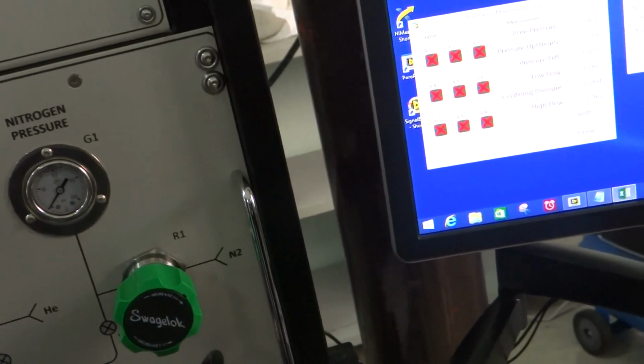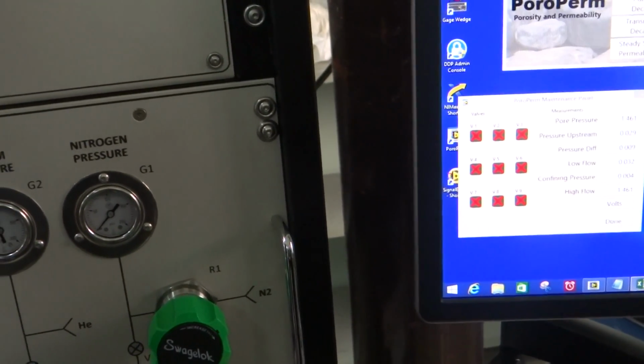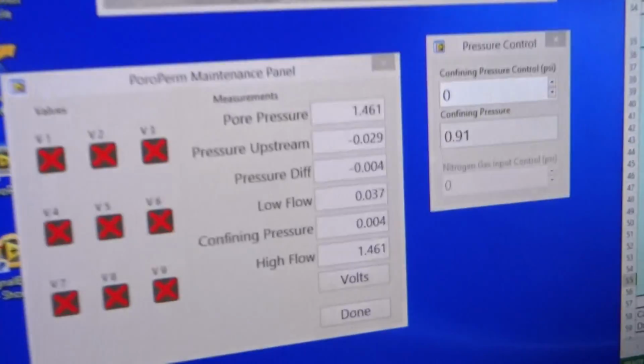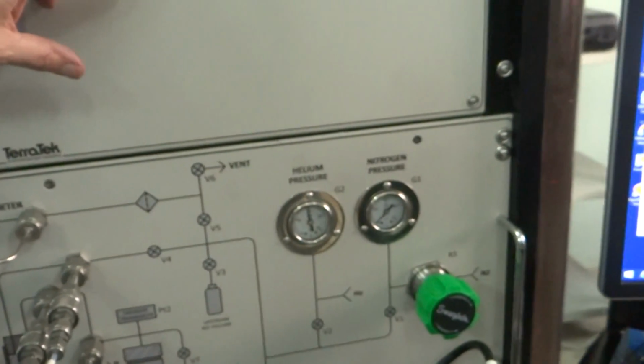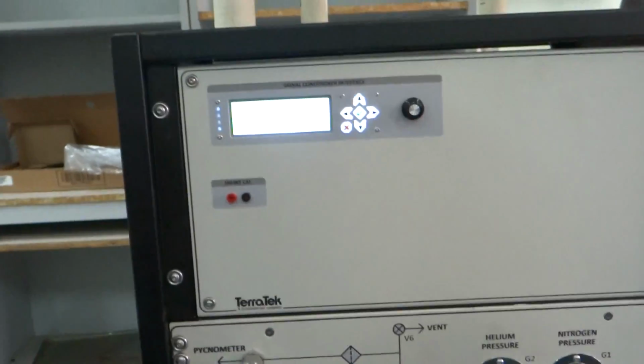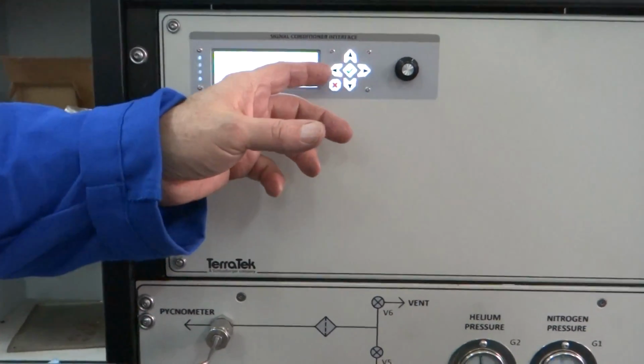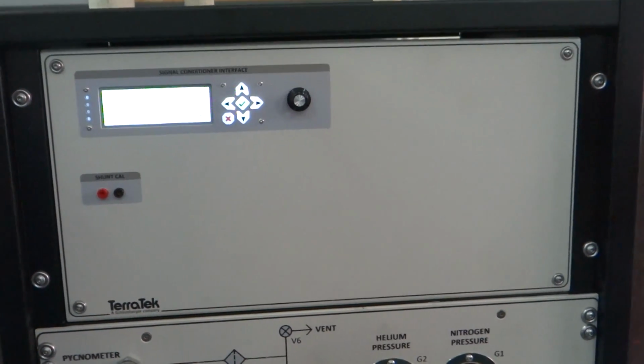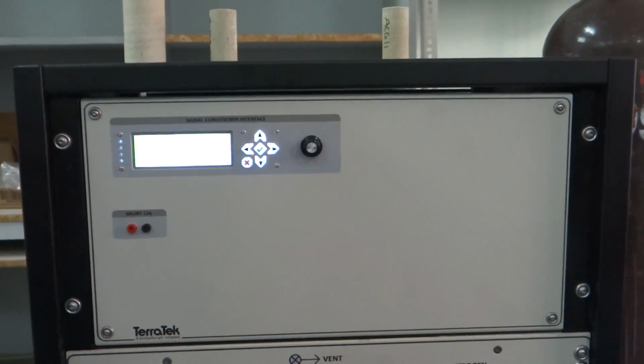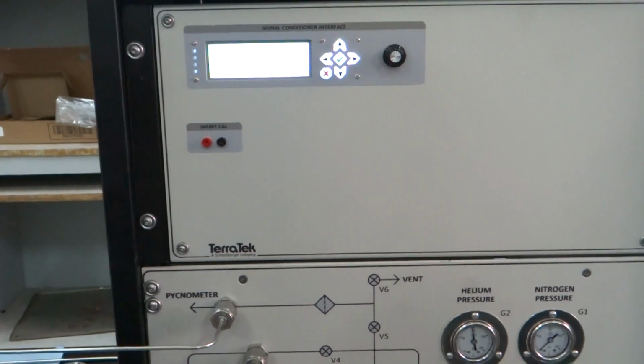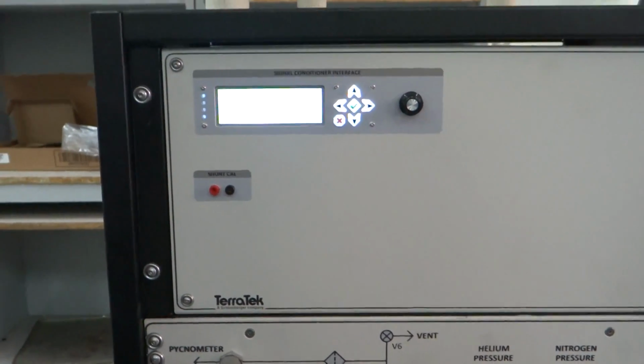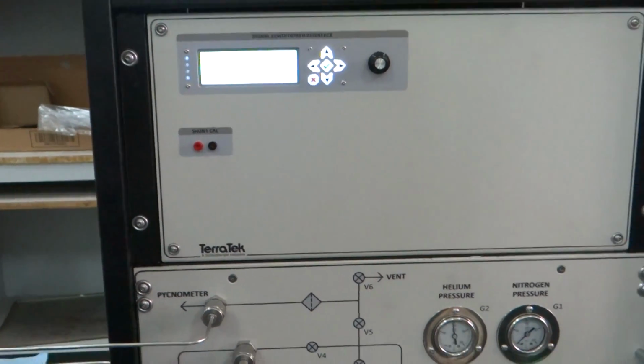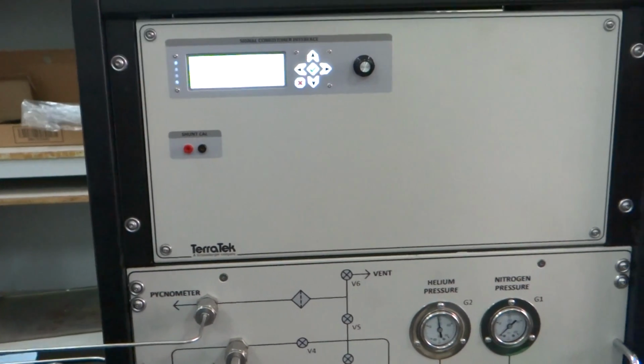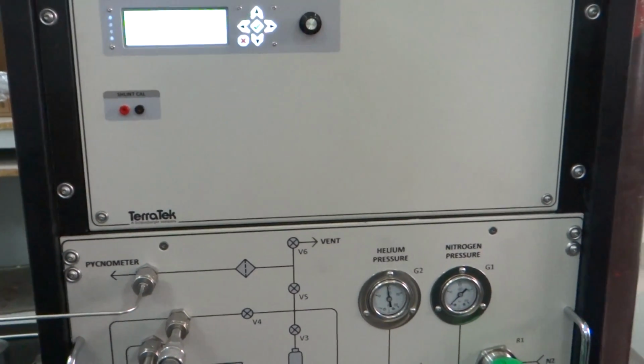Pressure difference. So you just adjust it to 0 if there's 0 pressure on the transducer. Oh, okay. Then the gain: you will apply full pressure to the transducer and adjust the gain until the voltage is a little bit less than 10 volts, because the A to Ds are from 0 to 10 volts. So if it goes over 10 volts, it'll saturate and won't read the value. So it has to be between 9.5 and 9.8 volts at full pressure. Full pressure. Okay, I know.